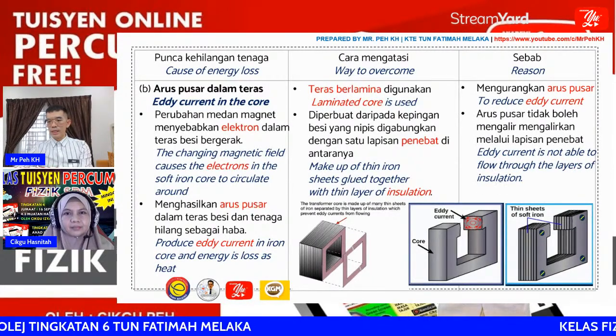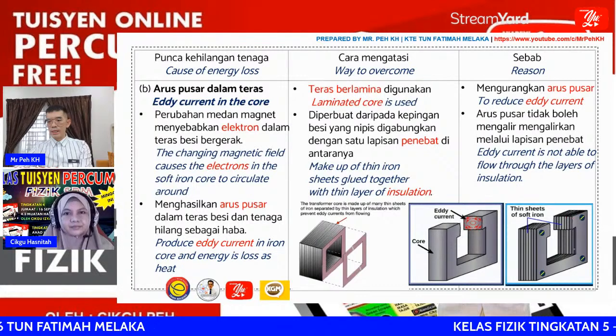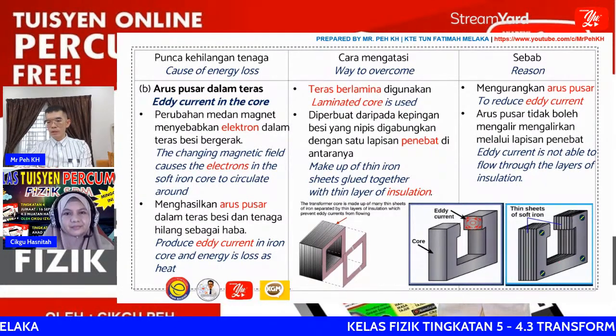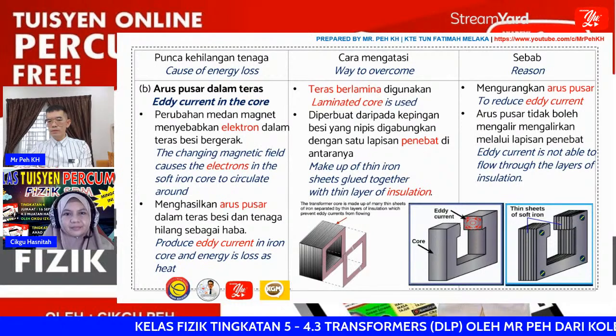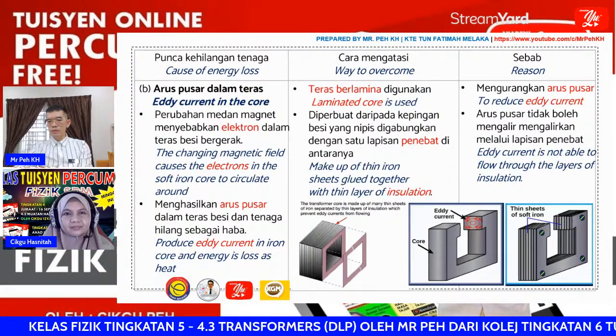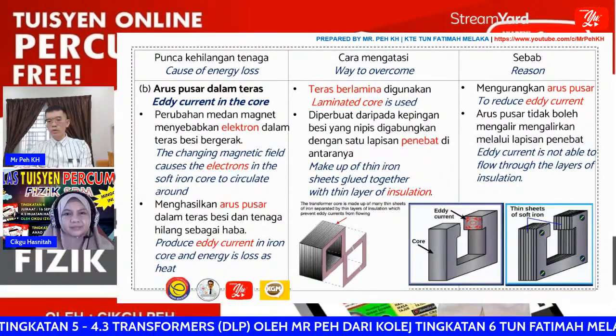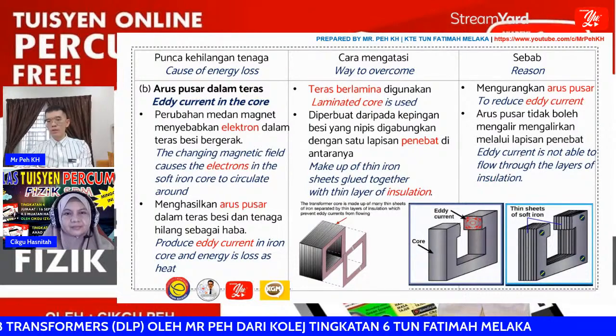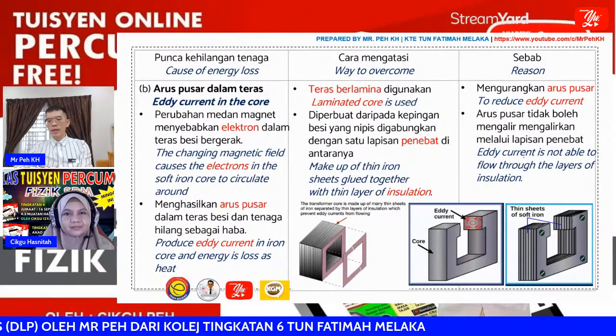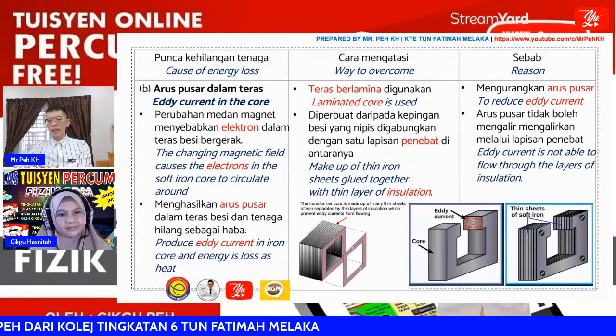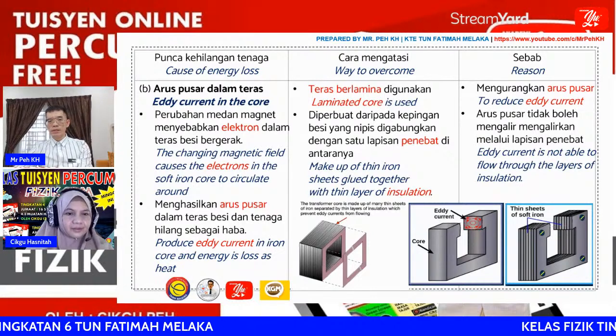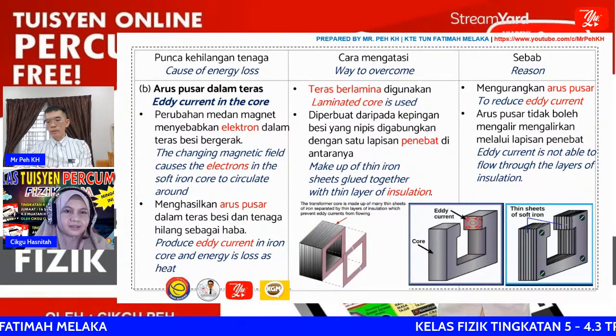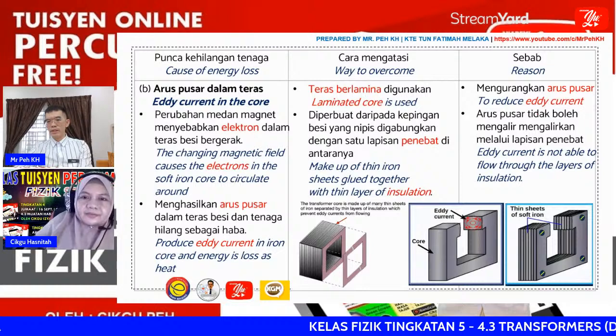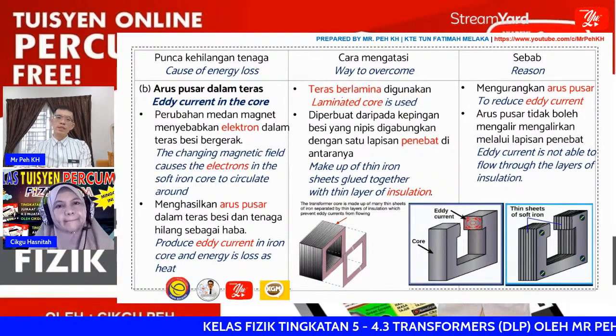You can see here an example - the thin sheets are glued up, and the glue is actually the insulator, which does not allow the eddy current to flow through the core of the transformer. So therefore the eddy current will be reduced if you use the laminated core.